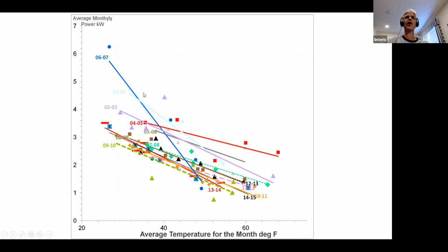You can also plot the average monthly bill against outdoor temperature, converting to average kilowatts per month. The slope represents the combination of your building's thermal efficiency and your heating system's efficiency. This particular winter we were on electric resistive heat, and you can see how dramatically that changed the slope. When the curves shift down, that reflects changes in the base load, like lighting or television use, things that are always there regardless of outside temperature. The weather-dependent load is mainly heating and cooling, and to some extent hot water.